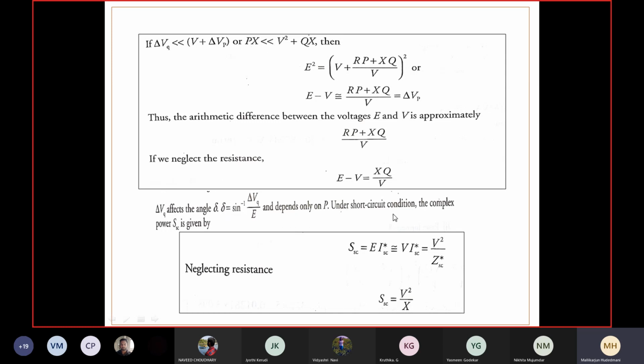Therefore, under short circuit condition, how can the complex power S_SC be written? It is E times I conjugate. During the short circuit this becomes V into I_SC conjugate, or in impedance form, V square by Z conjugate. If I neglect the resistance part of the impedance, the complex power during the short circuit is the square of the voltage divided by X. It is inversely proportional to the system reactance. When I maintain the voltage V, complex power goes as 1 by X. So the larger the reactance, the lower the complex power; the lower the reactance, the higher the complex power.